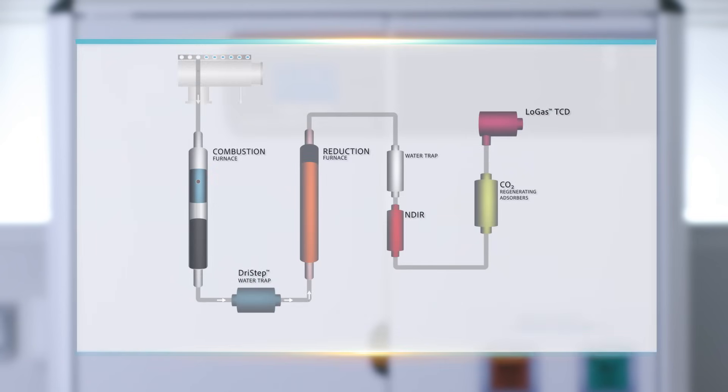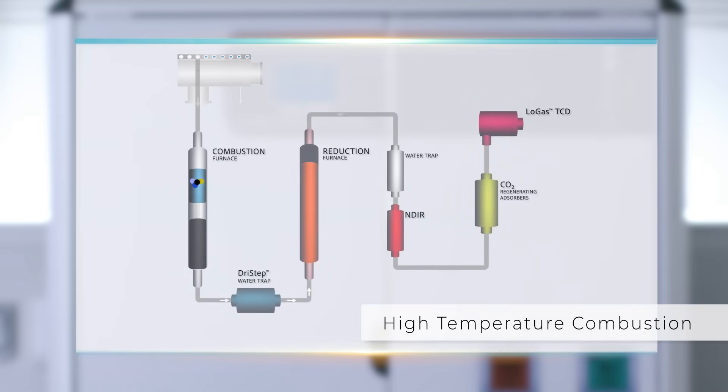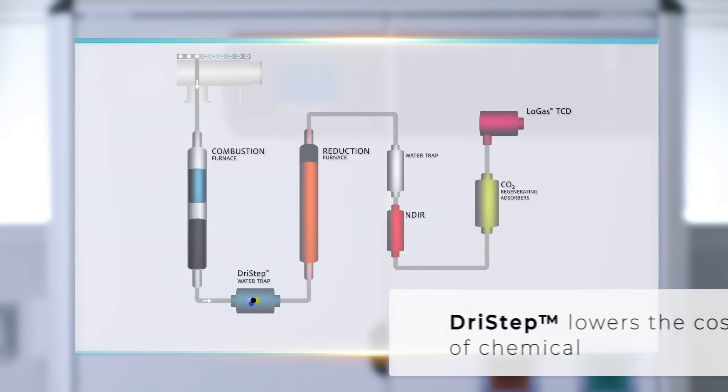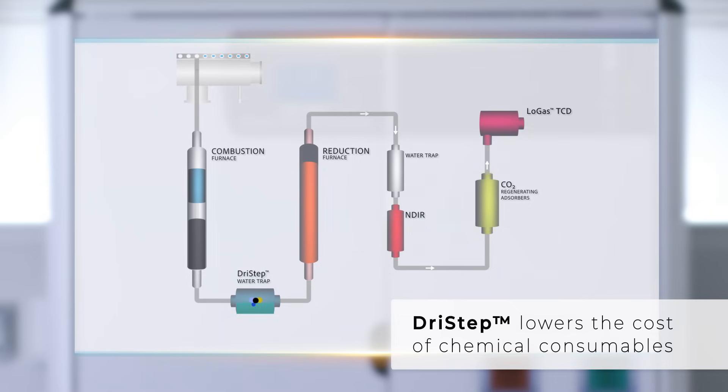The sample is purged with carrier and drops down into the combustion reactor where it is converted in its elemental compounds at a high temperature. The combustion gases are carried to the first water trap, the unique DriStep, trapping 99% of water, reducing cost of chemical consumables.